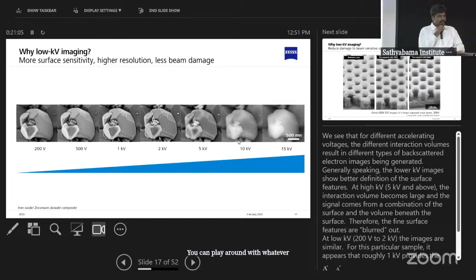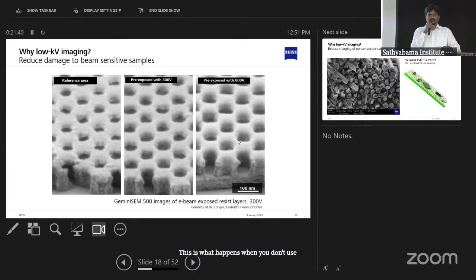And there's an example of a real-world photoresist used for lithography application. You can see here the image has been captured. This is the reference image. We captured it at 300 volts, no damage at all. When we move to 800 volts, you can already see that damage has started to happen. So this is the common topic called a beam-sensitive sample. And these are called SEM damages or SEM burns. This is what happens when you don't use optimized operating conditions for collecting the information.